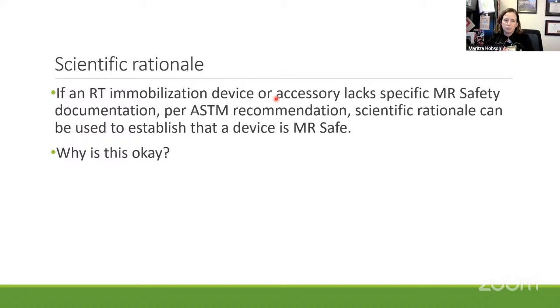So scientific rationale is also used. Say an RT immobilization device or accessory lacks specific MR safety documentation. Per ASTM recommendation, scientific rationale can be used to establish that a device is MR safe. So when can we do this? When the RT immobilization device or accessory is composed entirely of electrically non-conductive, non-metallic, and non-magnetic materials. Once you're ensuring these criteria are met, that means that magnetic force and torque are no longer a safety concern in an MR environment, and the risk of heating caused by gradient and or RF field interactions is reduced.